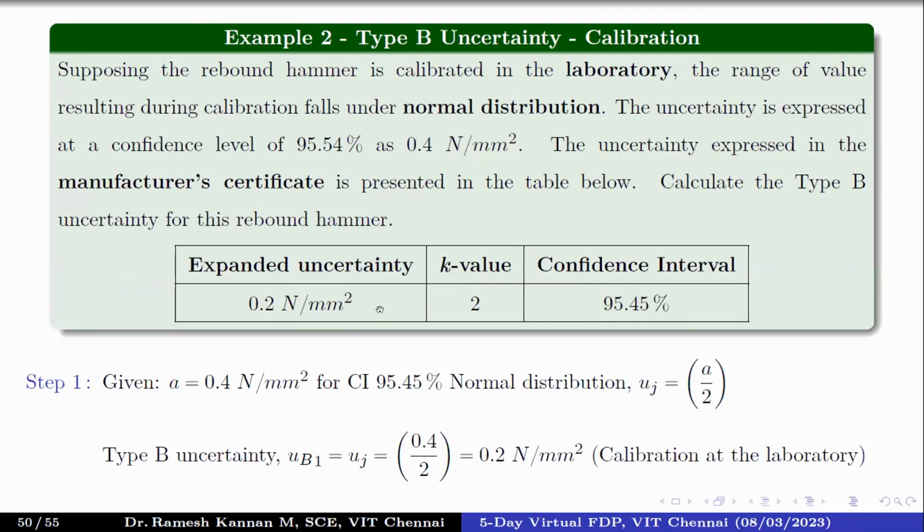Probably if you buy new equipment and try calibrating it, it will match exactly with the manufacturer standard. But as the years progress, wear and tear can happen, depreciation, excessive use can bring down the certainty of that equipment. So the manufacturer's and your calibration might have a differential value.